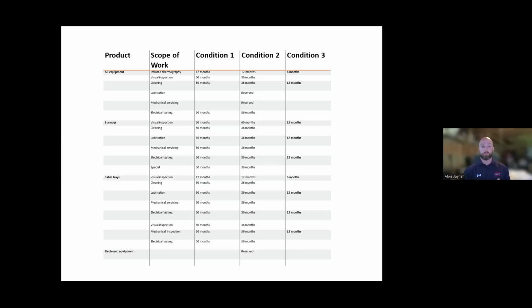Condition one right now, especially regarding cleaning and lubricating mechanical things, that is the de-energized maintenance we keep talking about. That's the time we'd be in there to shut things down, exercise the equipment, lubricate things again, and do special testing per each manufacturer's equipment.